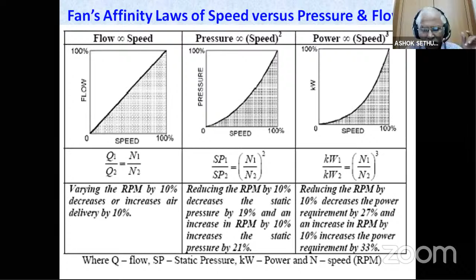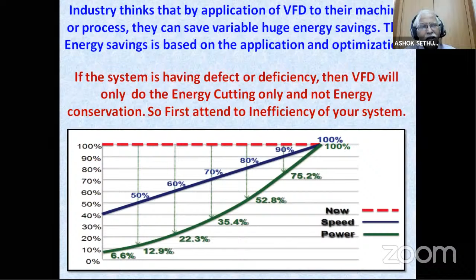This is what the industry is capitalizing on. You can do a lot of research on this, because the government is also thinking how to categorize the variable torque loads and constant torque loads. Variable torque loads have immense, huge potential for energy savings. This is what we are concentrating on here. So you can see at 80%, a 20% reduction in fan RPM gives almost only 50% of the power consumption of the given fan. A VFD or the motor can give only say 10 to 20%, whereas this impeller change can bring almost 30 to 40%.